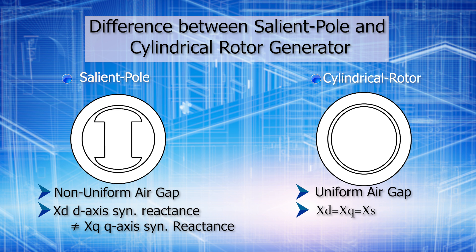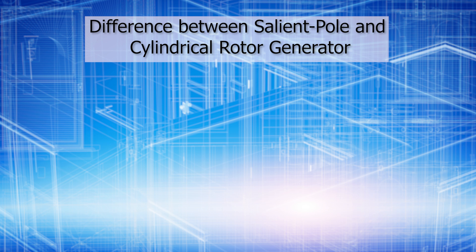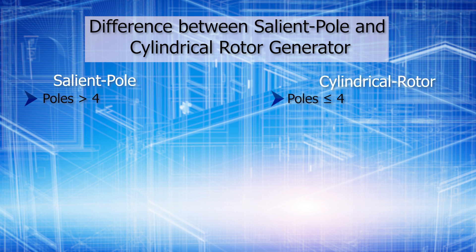All these features make the salient pole more suitable for low speed operation, whereas cylindrical rotor is preferred for high speed. In salient pole, the number of poles is generally more than 4; in cylindrical rotor, the number of poles is less than or equal to 4. More than 4 poles means slow speed; less than or equal to 4 means quite high speed. Under faulty conditions, salient pole has more chances of rotor deformation due to non-uniform air gap and air resistance, whereas cylindrical rotor has less chances of deformation due to its smooth surface and uniform air gap.